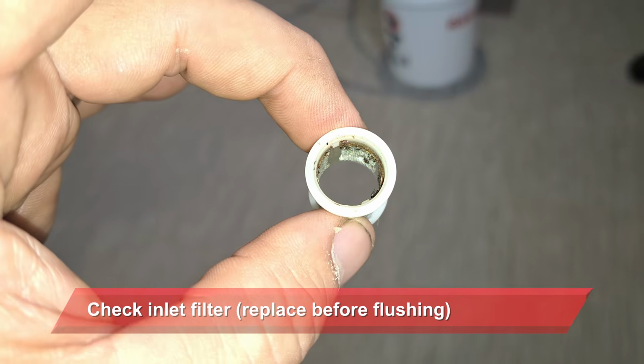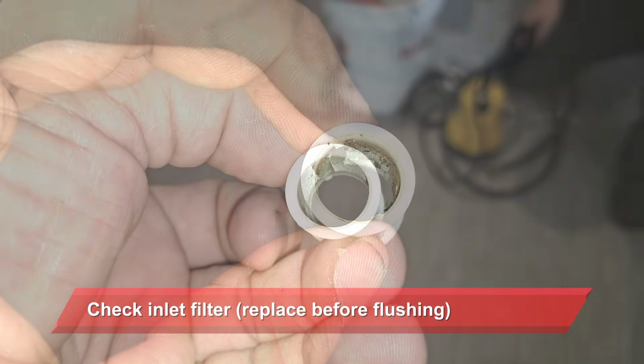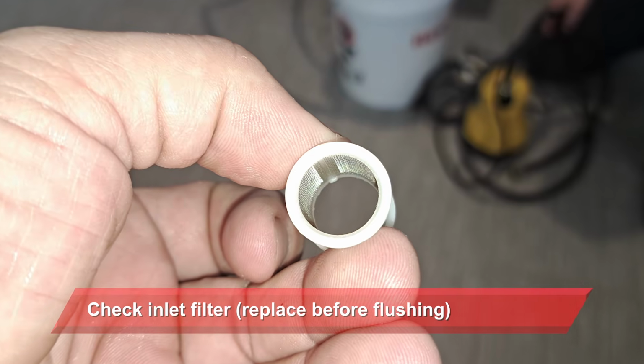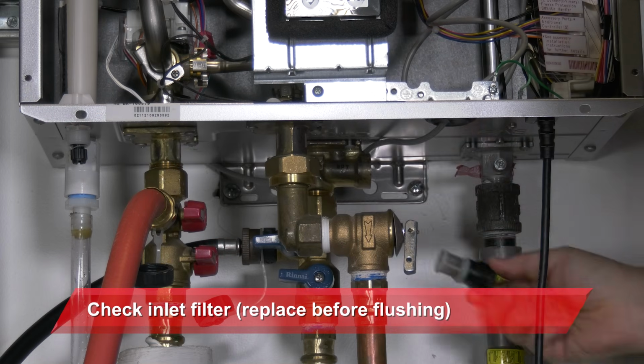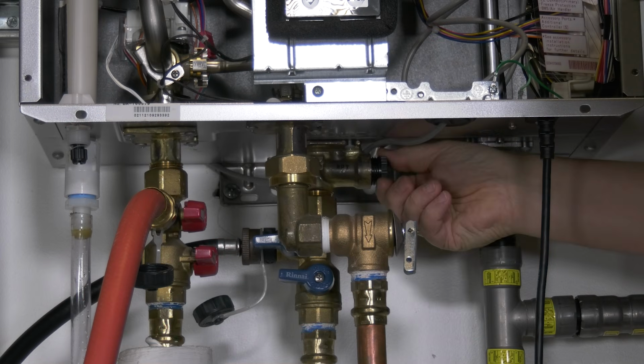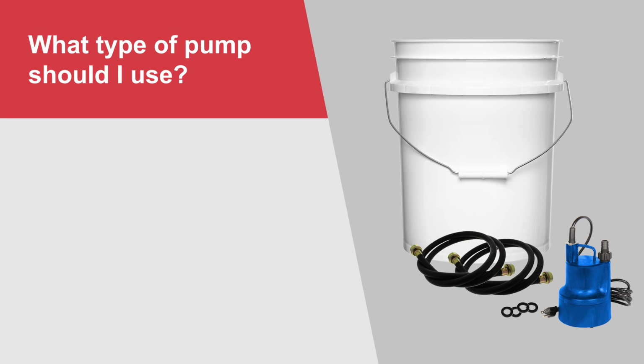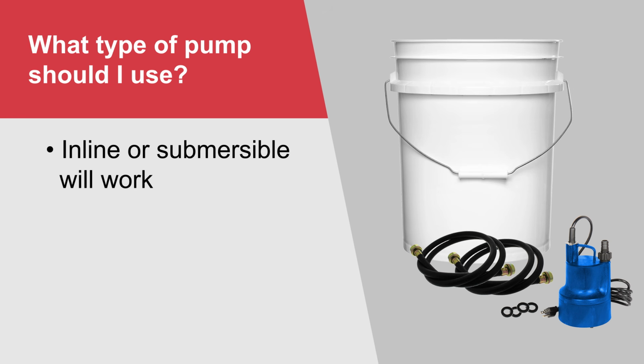At this point, we're going to check the inlet screen filter before we begin to ensure it's clean. But make sure this filter remains inside the water heater during the flush. Another frequently asked question is, what type of pump should I use? You can use an inline pump or a submersible. In fact, there are plenty of kits out there that include a submersible pump and the hoses. That's what we're using today.